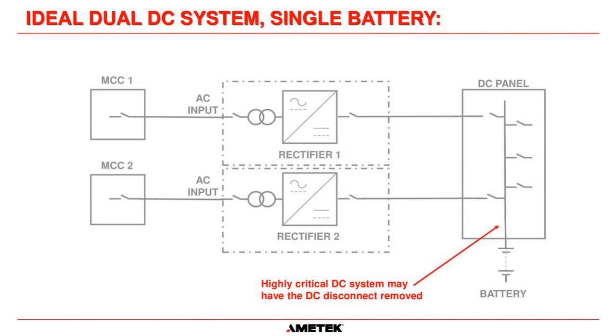And as I mentioned earlier, in some highly critical systems, they will not have a breaker between the battery and the DC bus here, because especially for DC lube oil pumps, you don't want anything to separate the power between that battery and the DC lube oil pumps on a turbine. So you want the most reliable form of power whatsoever, and sometimes they will remove the breaker from that arrangement.